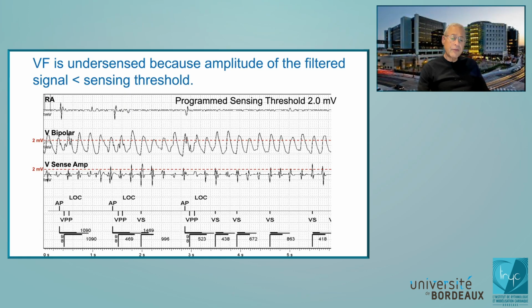So here is your sense amp filter, right? Now this is a pacemaker, and I'm displaying both signals for you. Based on what I just showed you, it's no surprise that if we compare the sense amp signals with the sensing threshold that's fixed, you can see they exactly match the sensed events as long as we're not in a blanking period, right? The lesson here is you need to know what signal the device is actually analyzing to make sense out of the marker channel. Okay.